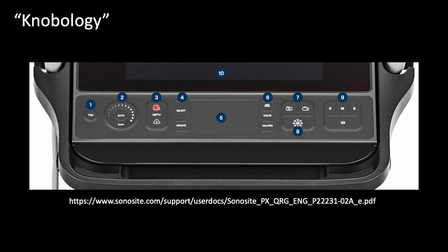Changing your depth is just simple click buttons. But here you have your gain. So you do this kind of like an old school iPod. You would turn the click wheel up here to where it's higher gain, or you would decrease it by going counterclockwise to where it's lower. Or you can turn on your time gain compensation, TGC, by this value here. So measuring things, you would have to select your caliper or calcs, and if you wanted to label something, you would have to press the ABC button.